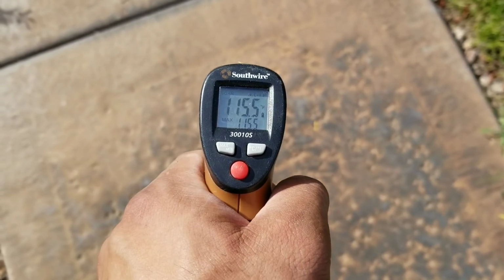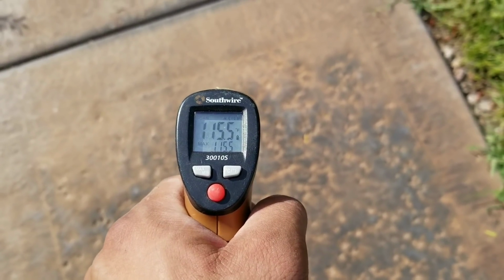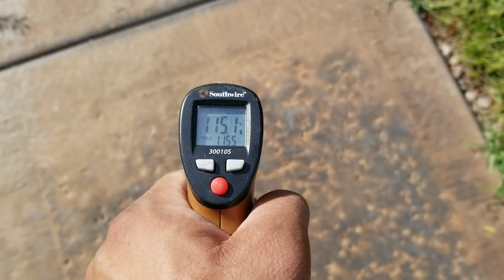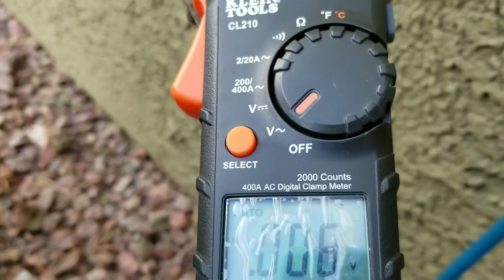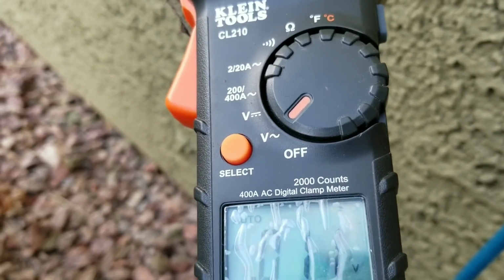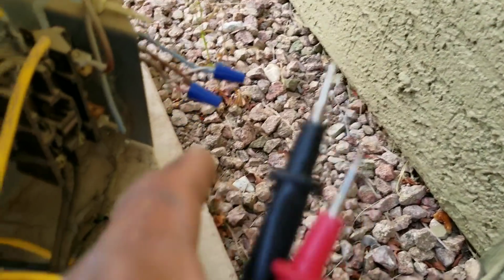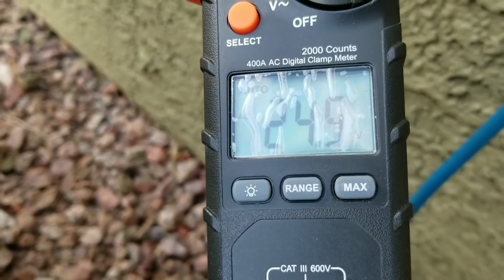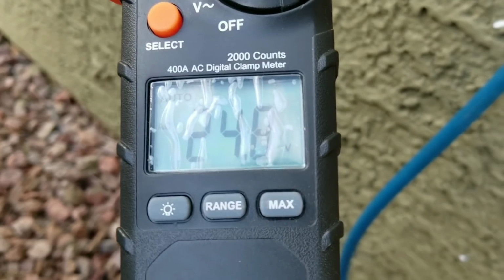Right now we're at 115 degrees. This is just the ambient temperature outside. I have my multimeter set to voltage, and what I'm going to do is take the low voltage reading on my contactor. And you can see here I have 24 volts.